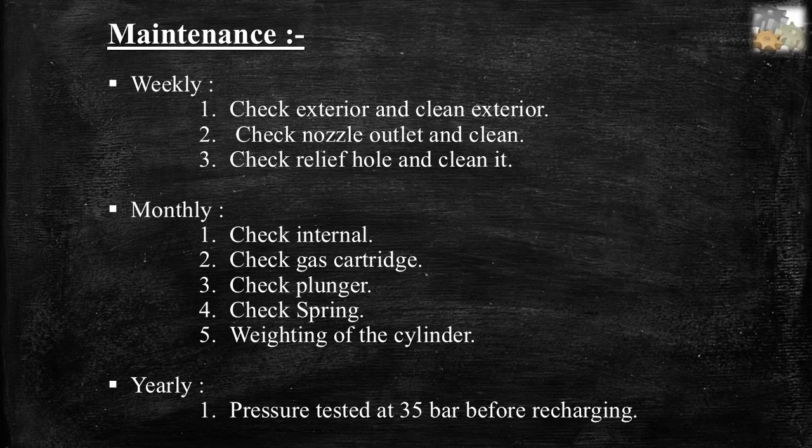Monthly maintenance: check internal components, check gas cartridge, check plunger, check spring, and weighting of the cylinder. Yearly maintenance: pressure tested at 35 bar before recharging.